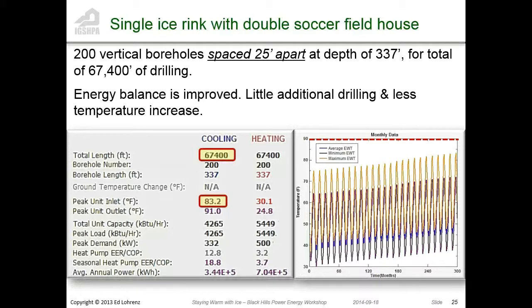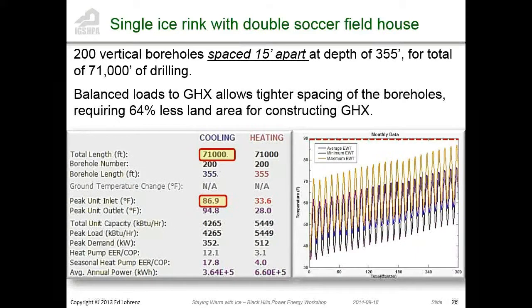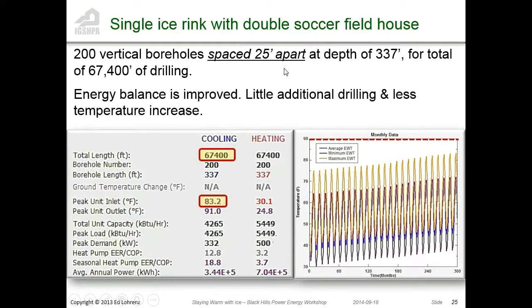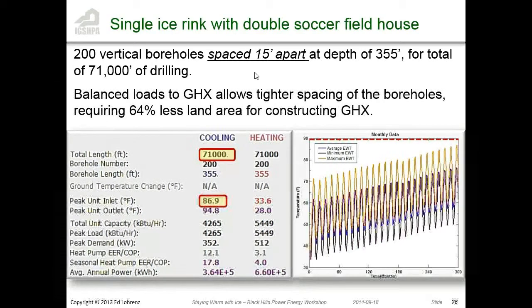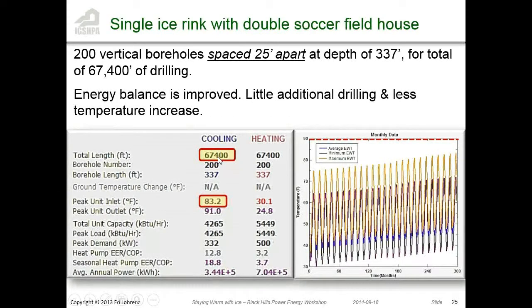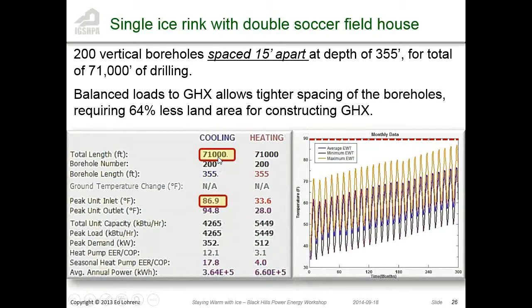Okay, one thing about once you've balanced the loads a bit more, what we found basically is that you can space the ground loops closer together. So in other words, instead of taking up more land area by spacing the boreholes, let's say 25 feet apart, you can reduce the spacing quite a bit, and without changing the amount of drilling that you need a whole bunch, because you're dumping energy in, you're pulling it back out. You're dumping it in, you're pulling it out. And the land area that you need, smaller.